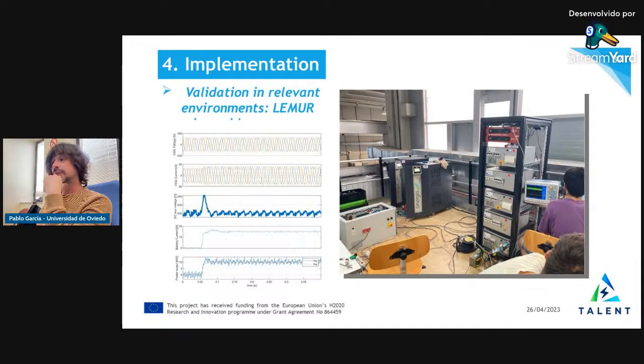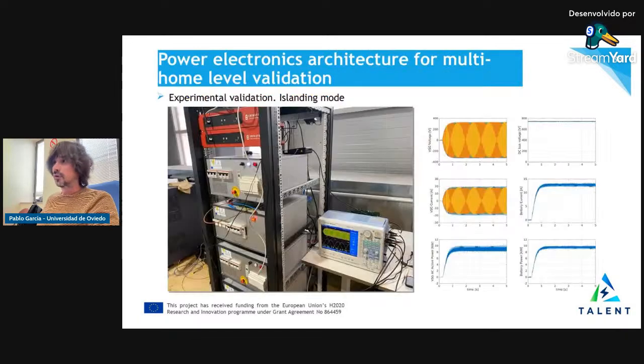This is the control once you have the IGBTs working; we need to interface with the inverter and the grid. This is the control of the 3-level NPC power converter, which has a switch for disconnection from the grid. We did this under two concepts: everything was done with virtual synchronous generator control, allowing us to work in grid forming or grid following mode, with a detail of the power converter and figures showing the transient behavior from the AC side.